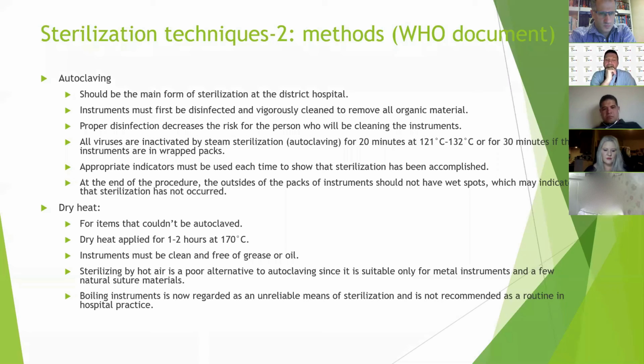It should be disinfected first and cleaned before being sent to SSD. The reason is we want to protect the staff there. It is left in the autoclave for 20 minutes at 121 to 132 degrees, or for 30 minutes if they are wrapped packed. And there are some indicators they put in the machine to indicate whether it has done its job or not. The dry heat is not as effective as autoclave, but it is applied for 1 to 2 hours at 170 degrees. And again, they have to be cleaned beforehand.